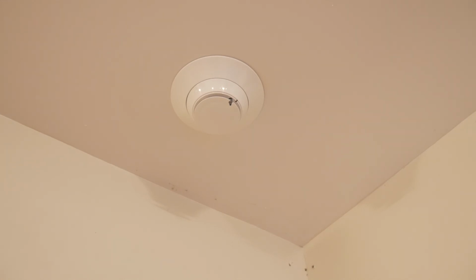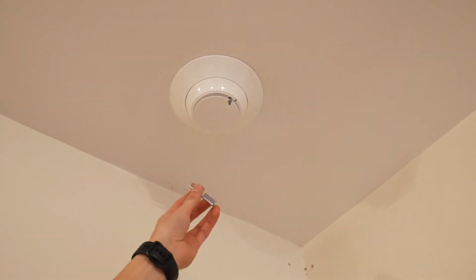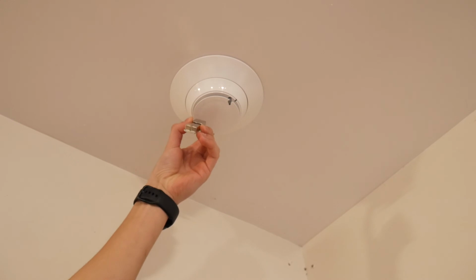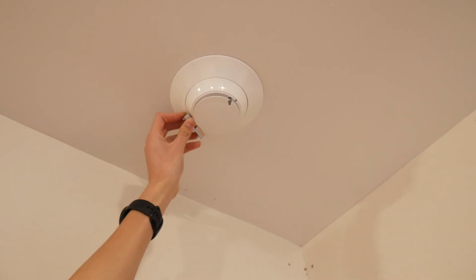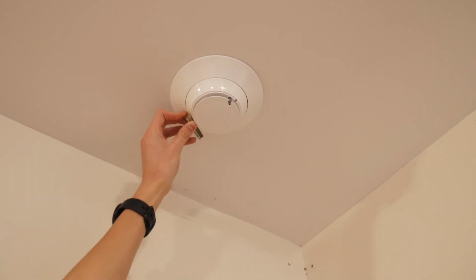Okay, right here we have our System Sensor detector. Well, this is supposed to be a Notifier one, but it's a System Sensor brand because they do work on this panel on FlashScan. So we're gonna test this by magnet testing it because I don't wanna use smoke right now. So anyways, we'll magnet test this. So let me find where the magnet is. Okay, it's right here. So I'll just put this here and wait for it to go into alarm.